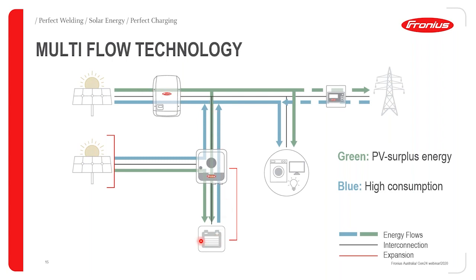Or with the multi-flow technology, you can take power from the panel to the inverter to your loads, at the same time from the battery to the inverter to the loads, plus also from the other inverter to the loads if you have a high load. We can also charge the battery from the panels directly, and also from the AC side to the battery. That's what we call the multi-flow technology with the inverter.